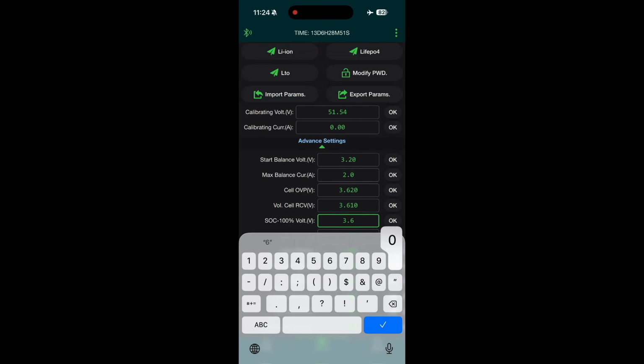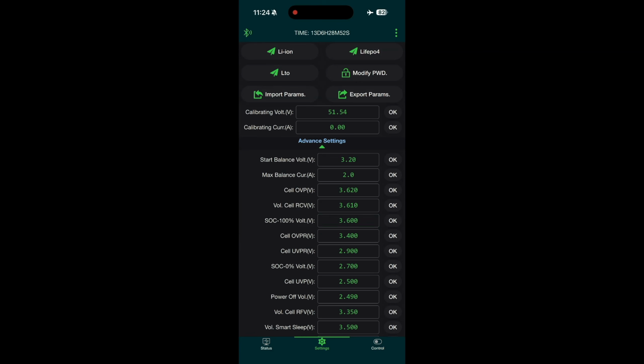Next is cell OVPR, over voltage protect reset. What happens is it charges up typically to 3.65, and once any one of the cells hits that, it stops allowing charge into the bank until it comes back down to whatever this setting is. So this is the reset point to allow charging to resume.